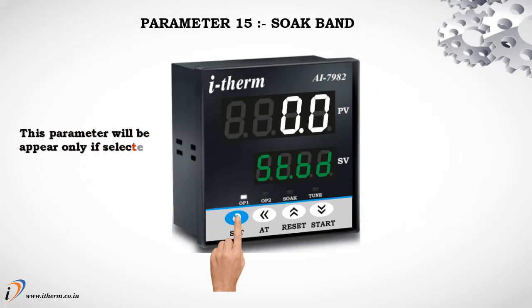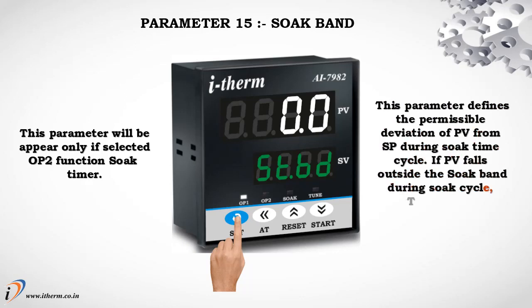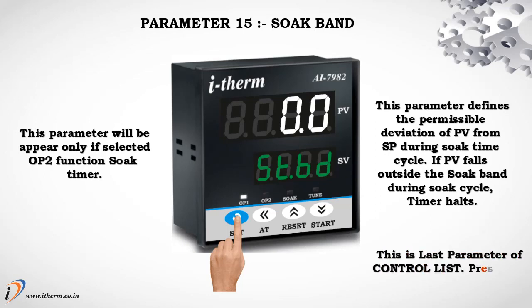Parameter 15: Soak band. This parameter will appear only if the selected output 2 function is soak timer. This parameter defines the permissible deviation of process value from set point during soak time cycle. If process value falls outside the soak band during soak cycle, the timer halts. This is the last parameter of the control list. Press Set key to enter in run mode.